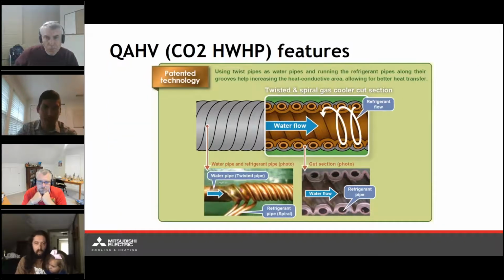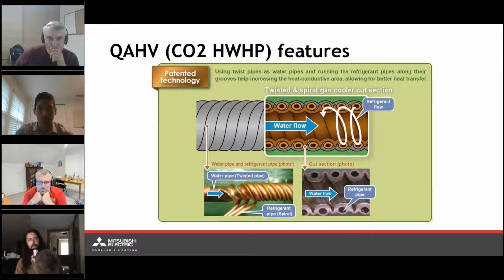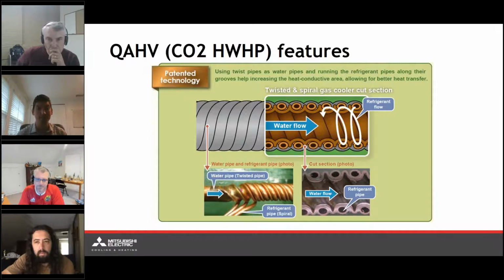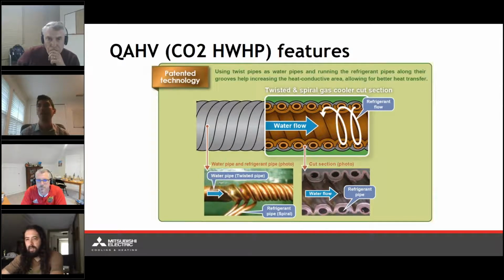Within the QAHV itself, within the condensing unit, this is going to be utilizing a brand new patented twisted and spiral gas cooler. So the 3 connected refrigerant pipes are wound around the twisted water pipe, maximizing the surface area for heat transfer. The continuous spiral grooves in the twisted pipe accelerate the turbulence effect of the water and also help to reduce the pressure loss within the heat exchanger, ultimately contributing to an enhanced efficiency. Now, this, coupled with an inverter scroll compressor within the VRF system, the QAHV is capable of significantly increasing the annual efficiency when compared especially to fixed speed systems that are simple on-off.